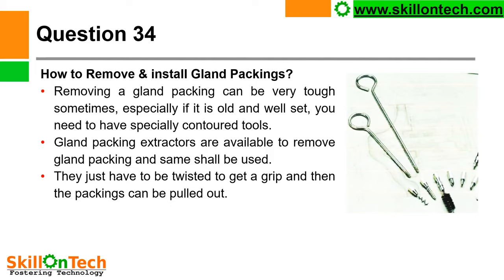How to remove and install gland packings? You can see a picture of a gland extractor here. Removing a gland packing can be very tough sometimes, especially if it is old and well set. You need to have specially contoured tools. Gland packing extractors are available to remove gland packings and shall be used. They just have to be twisted to get a grip and then the packing can be pulled out. Sometimes we open a suction valve to provide back pressure to the stuffing box to remove the gland packings. So that idea can also be used if you are finding it difficult to remove them.